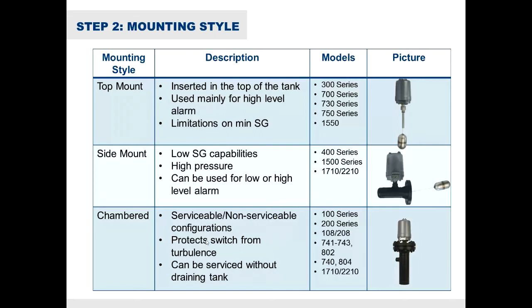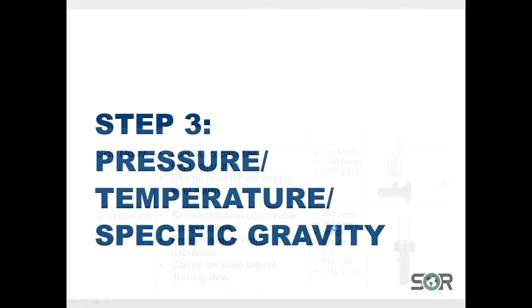A chambered configuration also allows you to service the level or swap out the level switch without having to drain the tank. If you need to change that level switch out, you can install isolation valves, close off those valves, and take the level switch off without having to shut down your process.